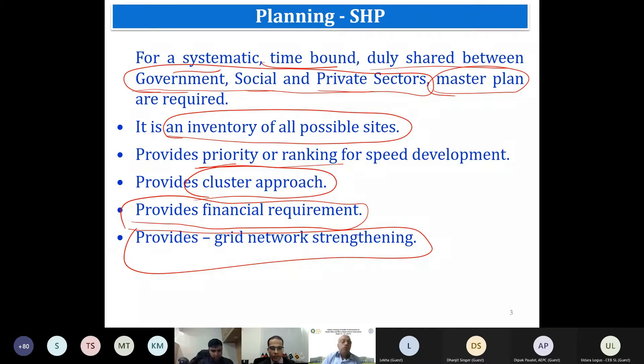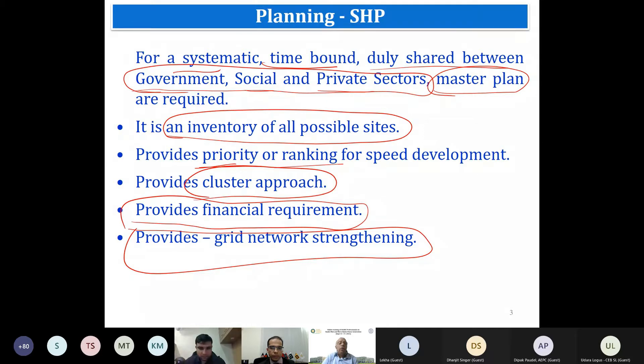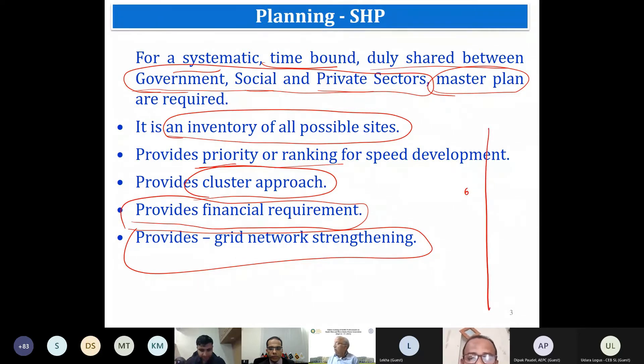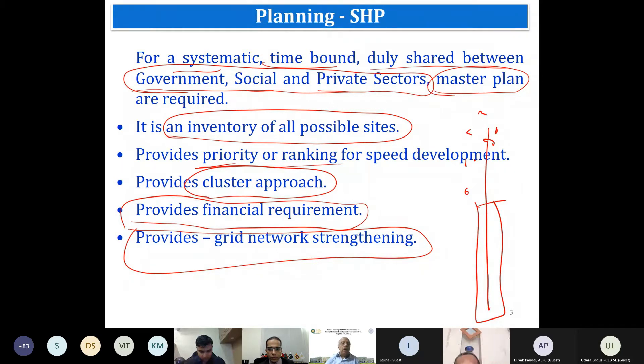Grid formation is a big challenge — you need to bring money, install the plant, and also take clearances because the grid often passes through forests, fields, and tribal areas where you need concurrence, land acquisition, or right-of-way. Also, when building a transmission line for one project, size it to accommodate future projects too — if total capacity is 50 MW, your transmission line must be strengthened accordingly.